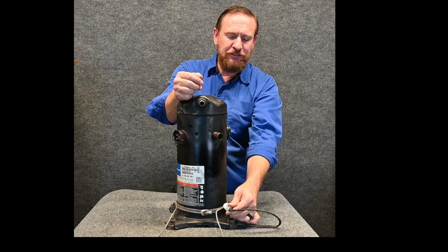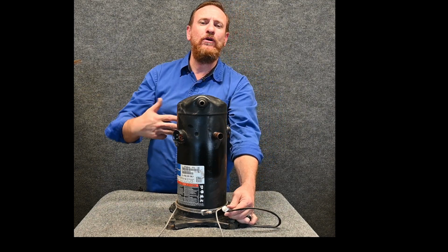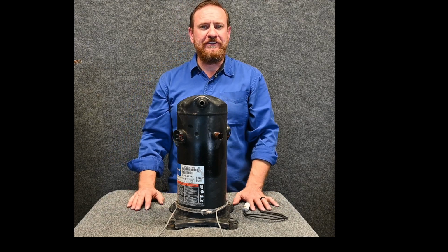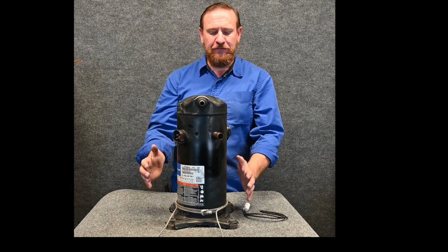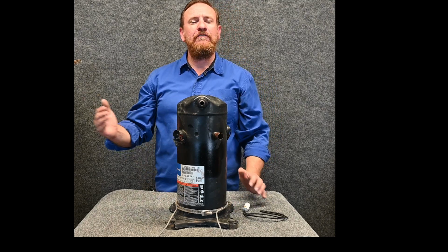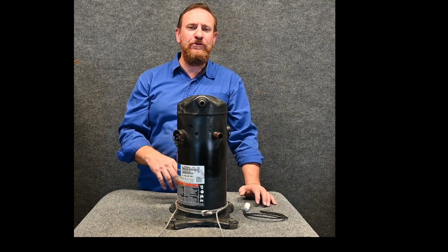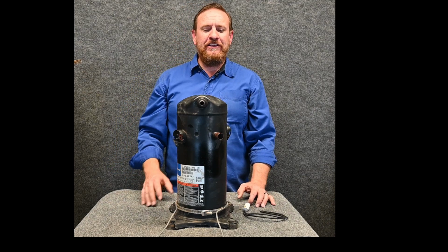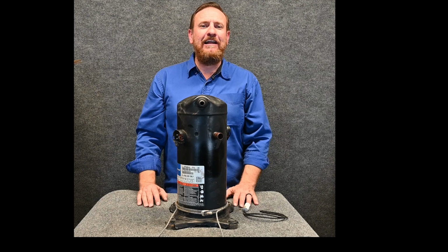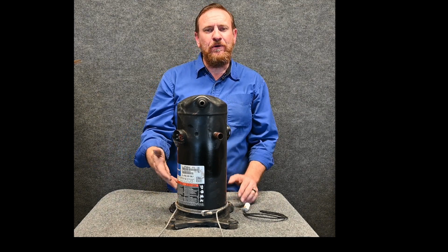We allowed electricity to go through here, and we kept the system warm. We kept the oil warm. There's several other types of them, but the whole idea was to prevent refrigerant migration. So if we kept this crankcase warm, refrigerant was less likely to want to migrate to it. Now the other thing is refrigerant also likes to migrate to the oil.